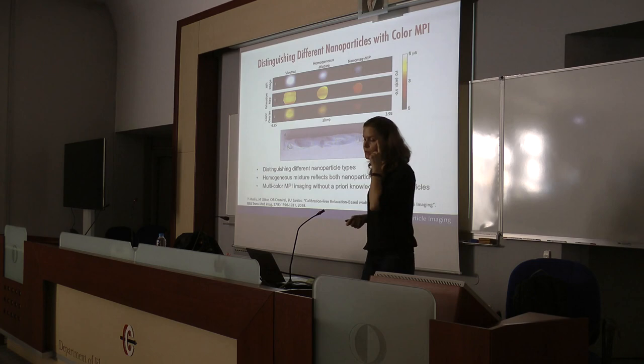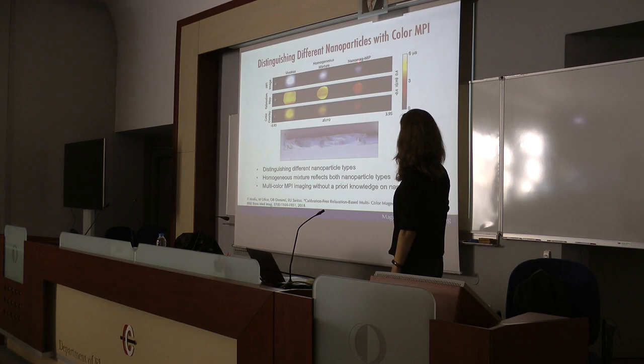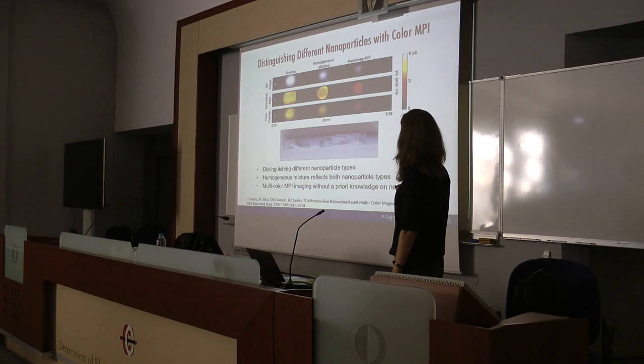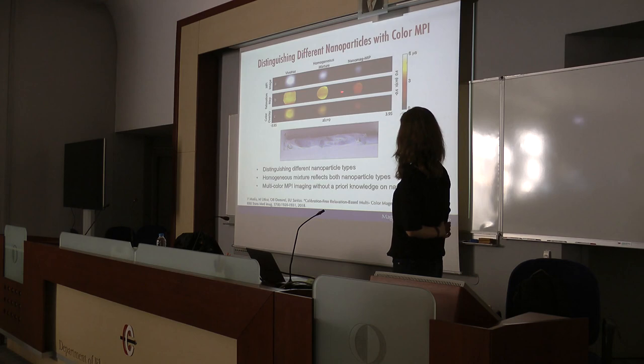We demonstrated our calibration-free color MPI technique on our scanner, showing the estimated time constants for two different types of nanoparticles and their homogeneous mixture. These time constants were estimated blindly without any prior knowledge about the underlying nanoparticles. We can get an MPI image showing concentration and simultaneously distinguish different types of nanoparticles. The homogeneous mixture shows a time constant that is almost the mean of the other two.